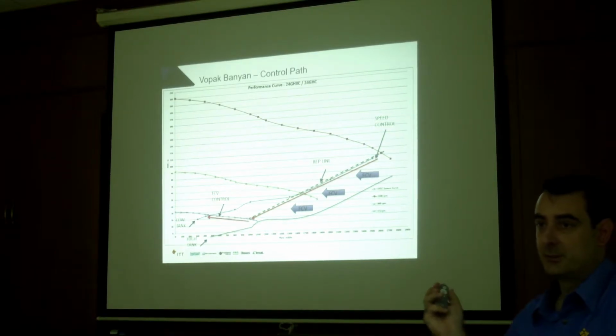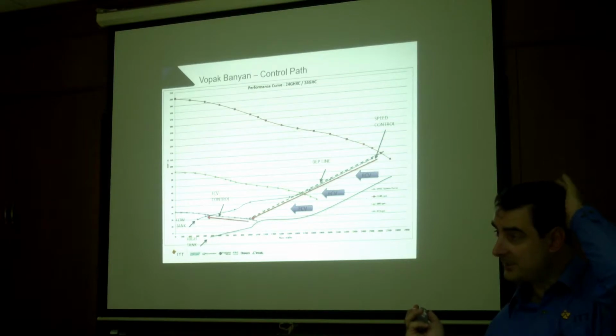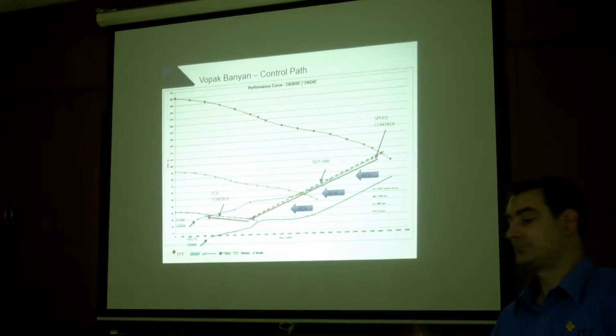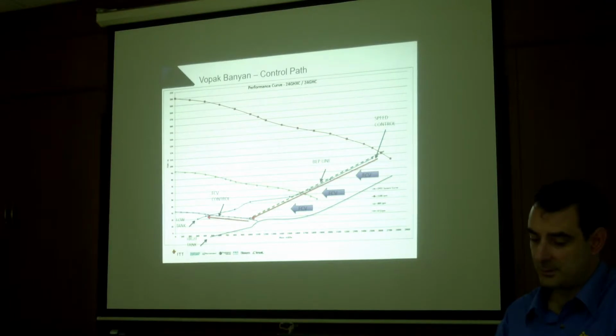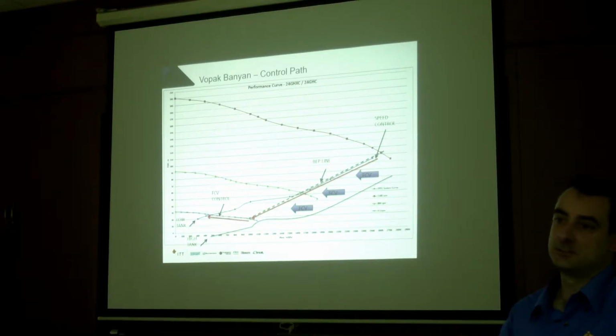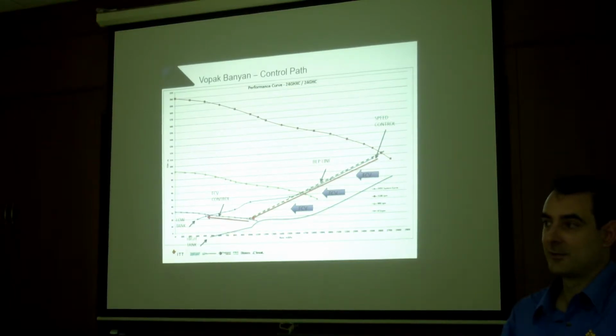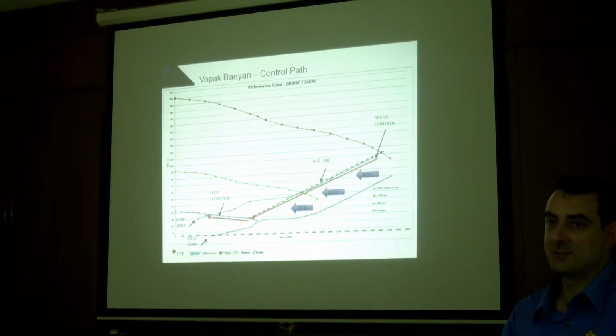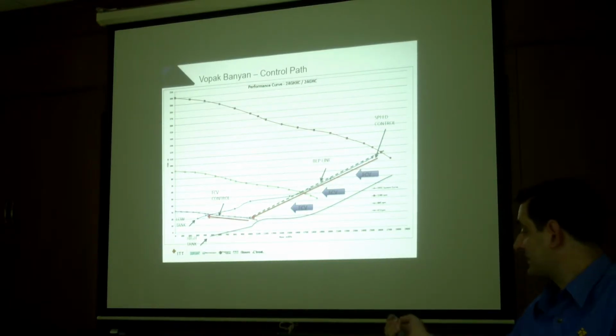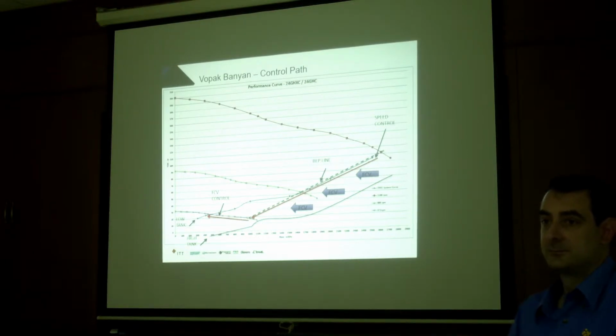That's in Singapore. There's 3 of them. We've been running since 2015, 16. In the last year, they've had 3 faults. The customer blames us. The pump's turned off. There's a red light flashing. When we do the analysis and we look at it, we've protected their pump and stopped $100,000 worth of damage every single time. Because they've actually had problems where they've had a valve shut and they didn't know about it and they're operating here. So we fault very fast. They find it annoying, we find it satisfying.